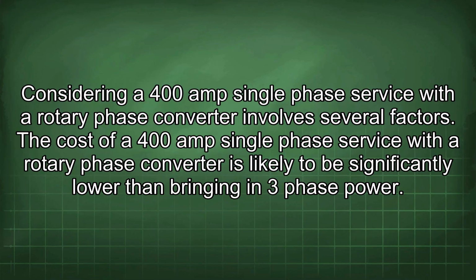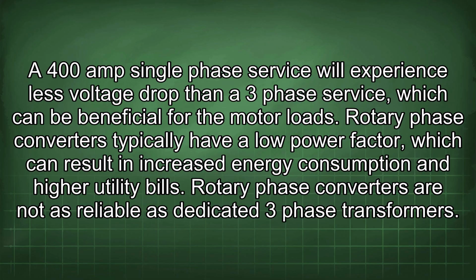Considering a 400 amp single-phase service with a rotary phase converter involves several factors. The cost of a 400 amp single-phase service with a rotary phase converter is likely to be significantly lower than bringing in three-phase power. A 400 amp single-phase service will experience less voltage drop than a three-phase service, which can be beneficial for the motor loads.